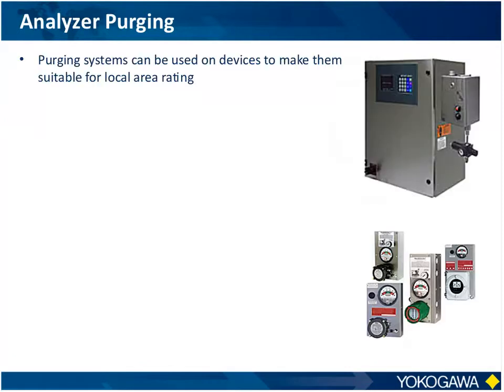One of the solutions we use for these packages is, if the analyzer doesn't meet the requirements for the area, you can purge the analyzer itself. For example, let's say I had an analyzer that doesn't meet Division 2 requirements, or that Australian code I was talking about.